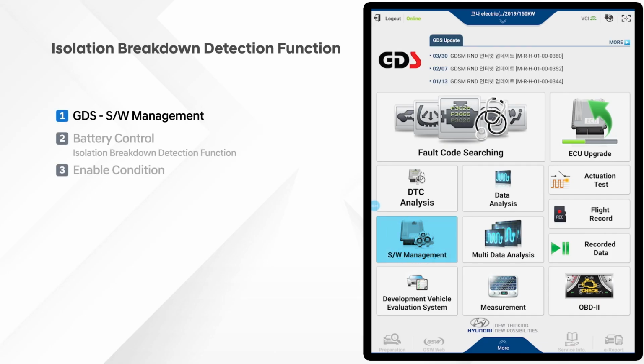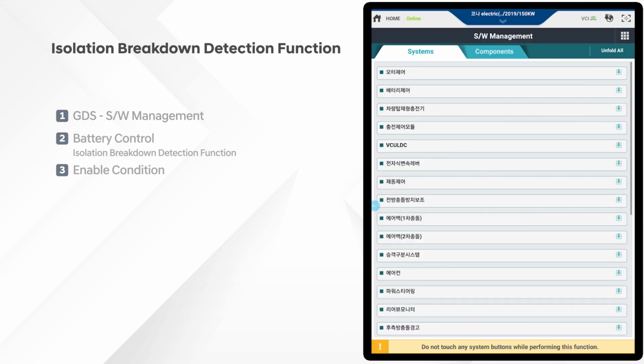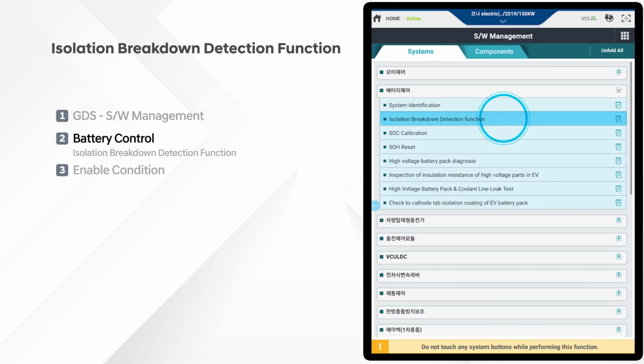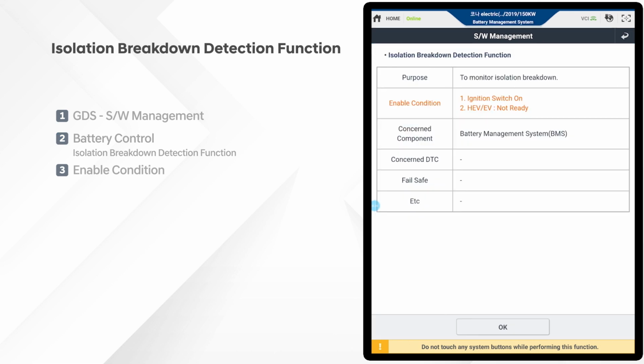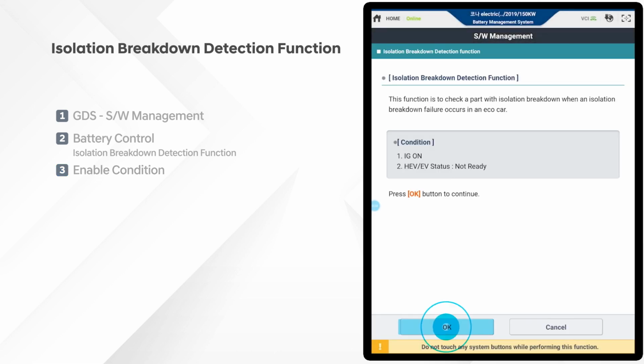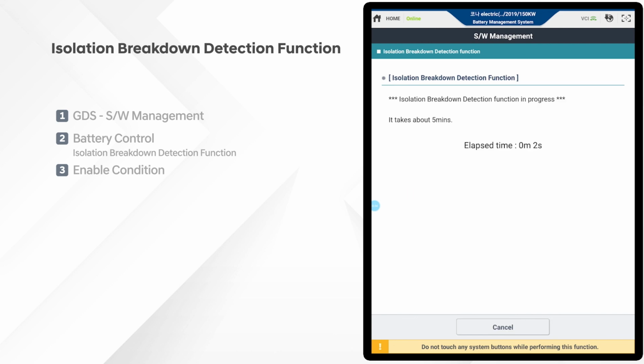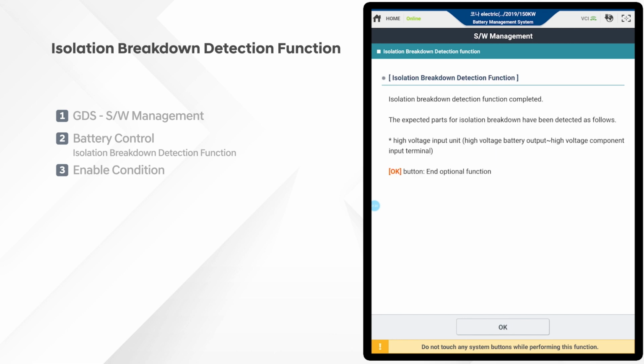Select Software Management. Go to Battery Control and select Isolation Breakdown Detection Function. Confirm the Enable condition and select OK. This test is conducted in 3 steps as follows, and if there is no problem, it takes about 5 minutes.